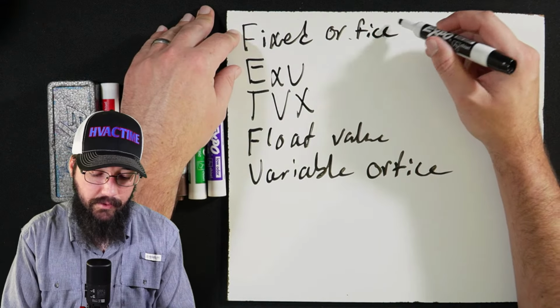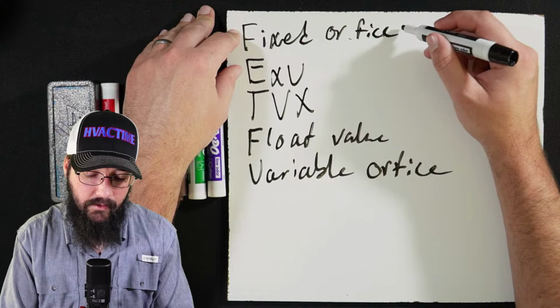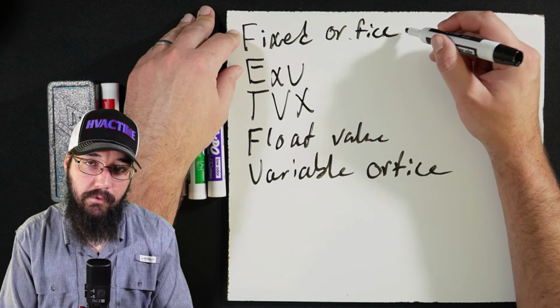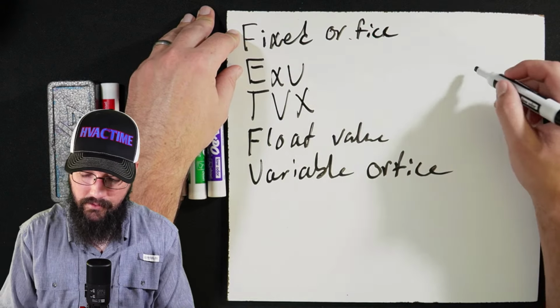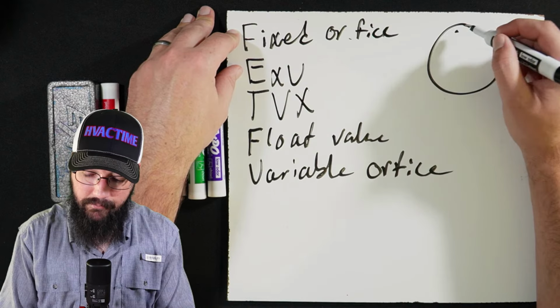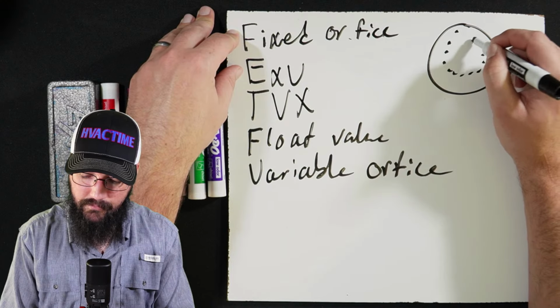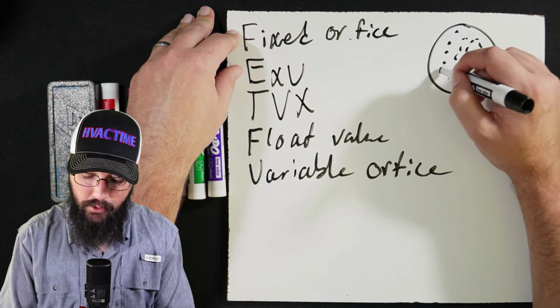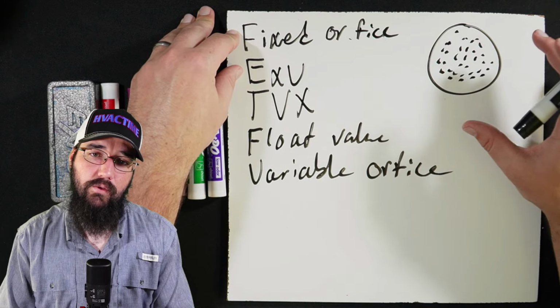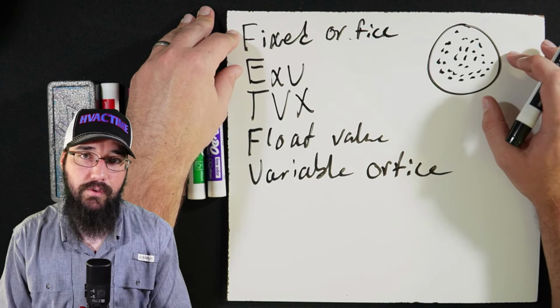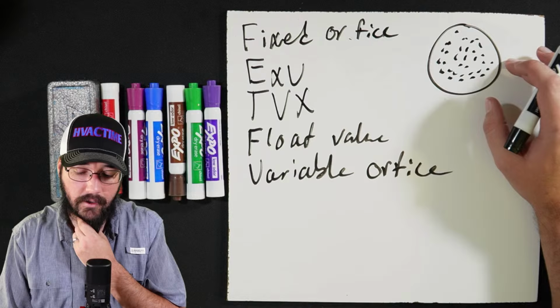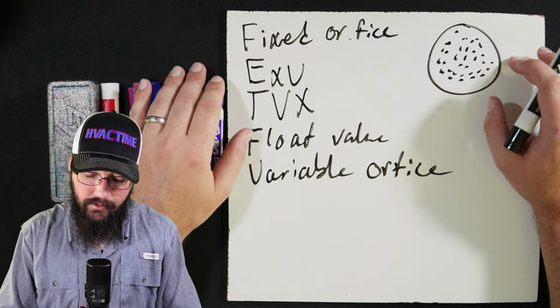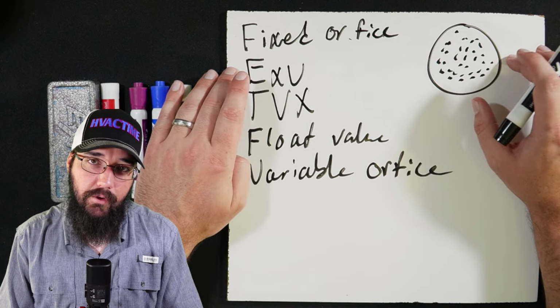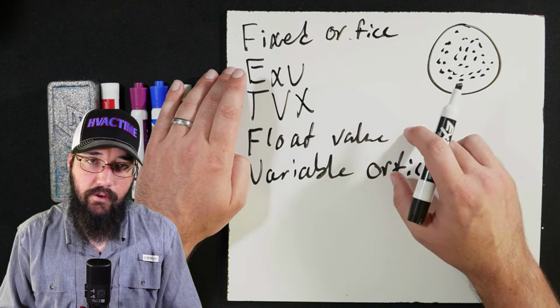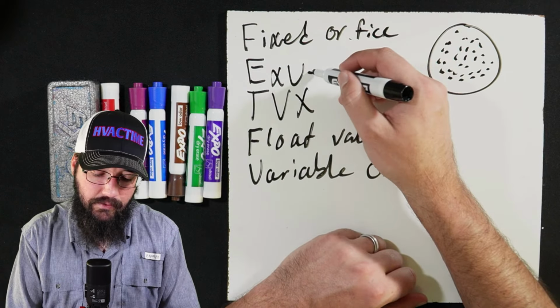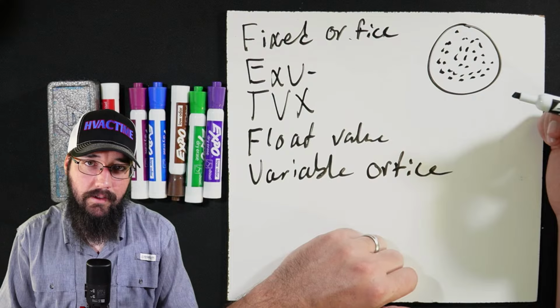Now, people that use different types. York was using fixed orifice in the beginning before they went to a variable orifice. And this is literally just a perforated plate. It's a big round disc with a bunch of engineered holes, perforations that create a pressure drop as the refrigerant goes through. Trane still uses these to this day, and Carrier, on their flash tank we talked about earlier in the stream, uses these in conjunction with their float valves as well. EXVs, most everybody uses to some capacity.